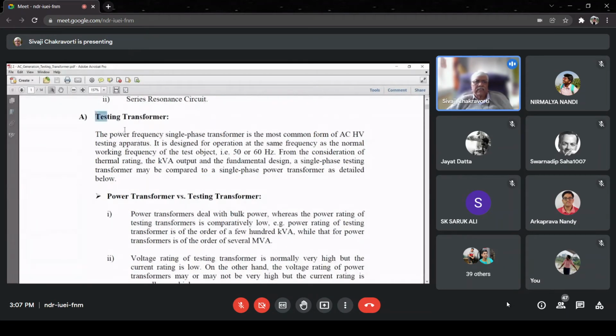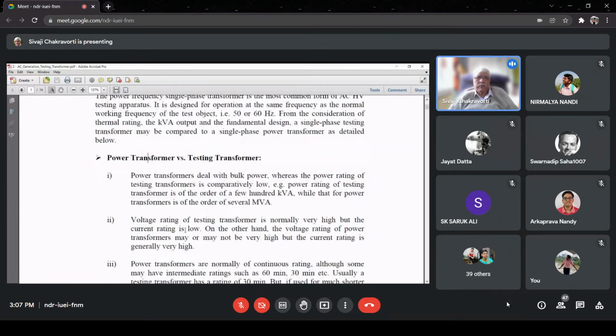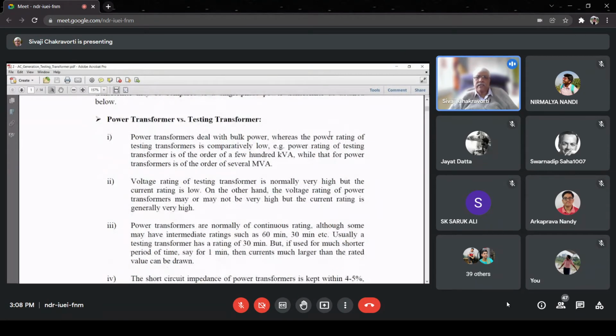First, I will start with the testing transformer, because the transformer is an equipment most probably you are already aware of, that this is used so widely. Now, there are transformers in our power system which are called power transformers. But what we are talking about here is not a power transformer. We are saying it is a testing transformer. That means it is used only for testing. Now, naturally, you should ask me, what is the difference? Is it the same? Well, they are not the same. So we have to tell you what the differences really are.